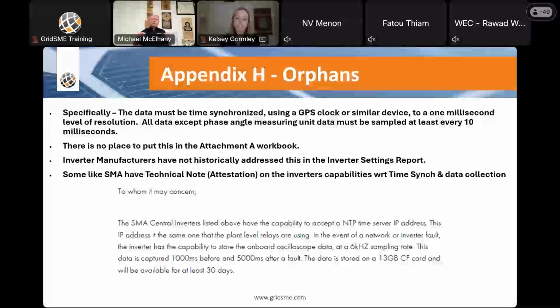So again, working with CAISO, we can either get this through an attestation, like some inverters, like SMA does. They have a 'to whom it may concern': these inverters have the capability to meet the Appendix H requirements for time syncing and for data sampling. Or we can get additional information, upload that into RIMS at the bucket 3 timeframe to provide the CAISO review to have that. Because if they don't get that confirmation, they will kick it back. And every time, I'm not trying to throw them under the bus, but every time they have any little thing that we have to respond to, that resets their clock for when they're going to finalize their review. So even if we turn it around in one day, it might be another 2 weeks to 4 weeks before we get the approval at the bucket 3 level.